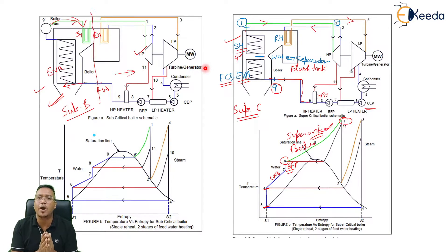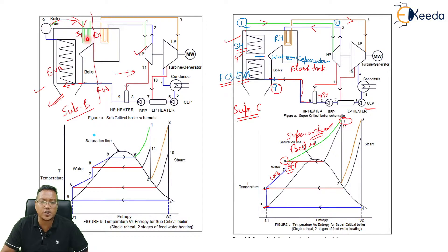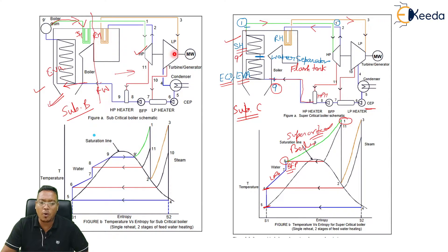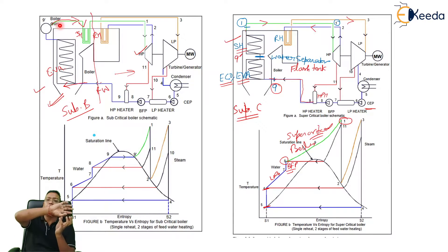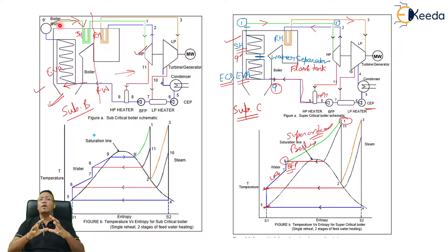How does a supercritical boiler work? First, this is the subcritical boiler. The steam from the drum goes into the superheater, then superheated steam goes into the HP turbine. After expansion in the HP turbine, steam goes into the reheater, then into the LP turbine, then into the condenser. From the condenser through CEP and BFP it goes into the boiler, into the evaporator, then evaporator to drum. From the drum, steam separates from water and goes into the superheater. This is the working of a subcritical boiler.